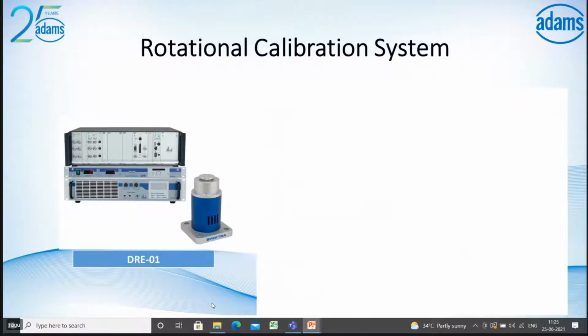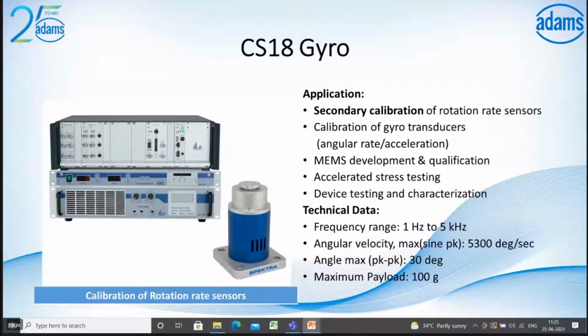This system is specially developed for the calibration of dynamic angular rate measurement sensors. CS18 for the gyro sensors calibrations is a secondary calibration of rotation rate sensors, especially developed for device testing and characterizations from the frequency range 1 Hz to 5 kilohertz. The maximum angular velocity can go up to 5000 degrees per second, and the maximum angle you can go up to 30-degree peak to peak. The maximum payload, that's the sensor mass, is up to 100 grams.